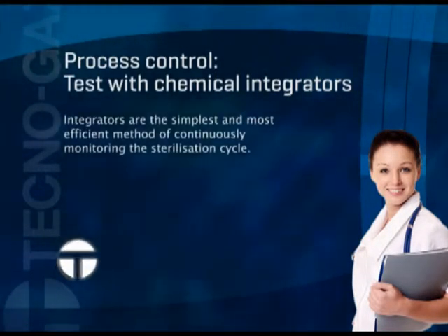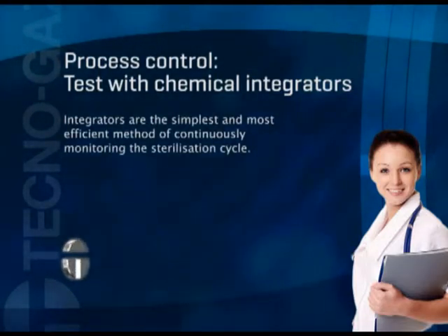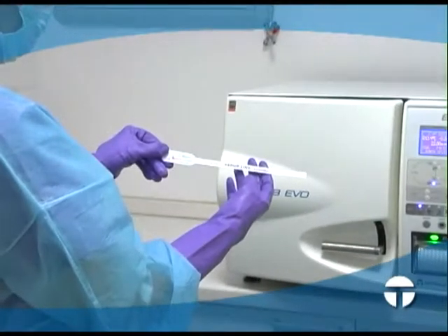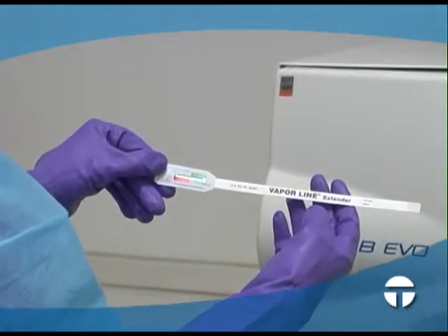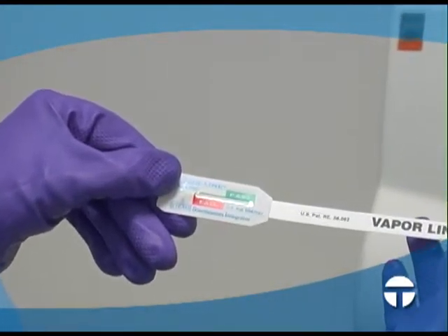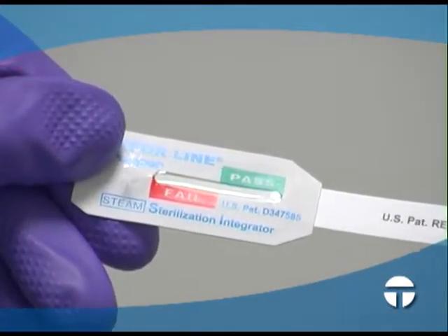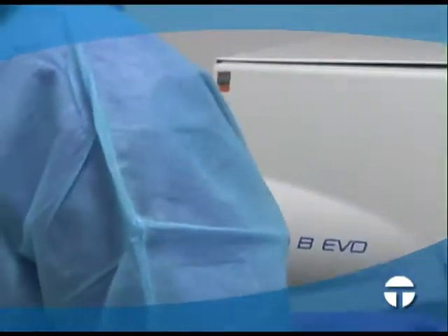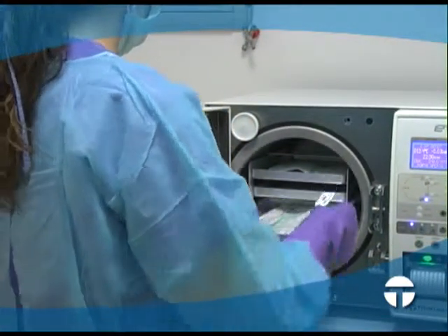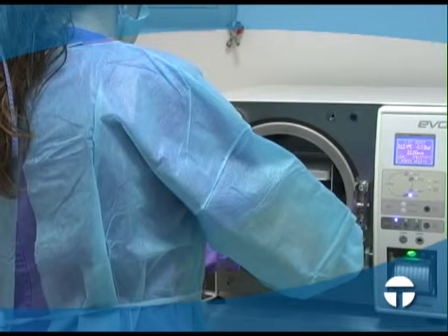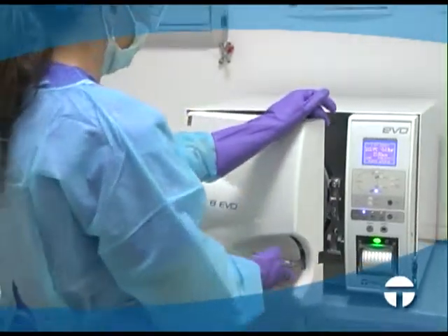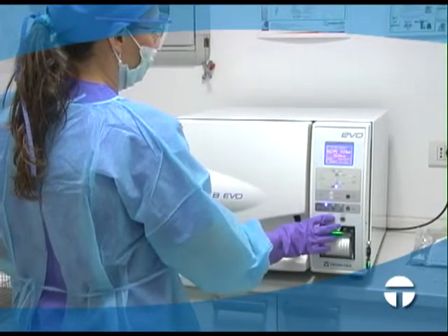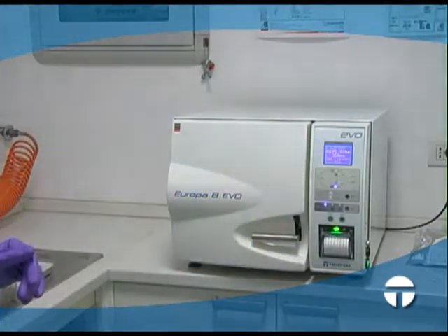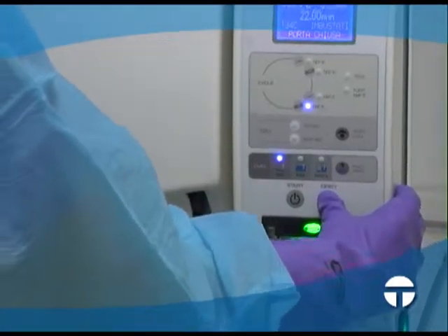Test with chemical integrators. Integrators are the simplest and most efficient method of continuously monitoring the sterilization cycle. Place an integrator on the upper, central, and lower trays, which may also contain loads. Alternately, insert integrators into each package containing material to be sterilized. Close the door, select a normal sterilization cycle, and start it. At the end of the cycle, remove the integrators and check the response generated.